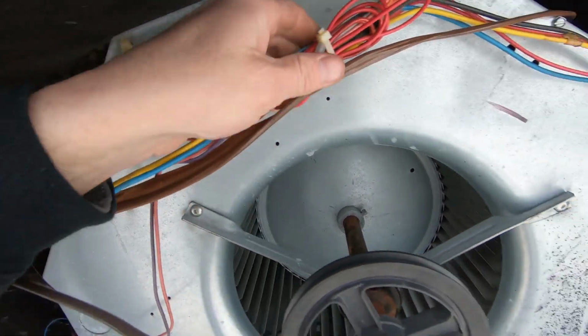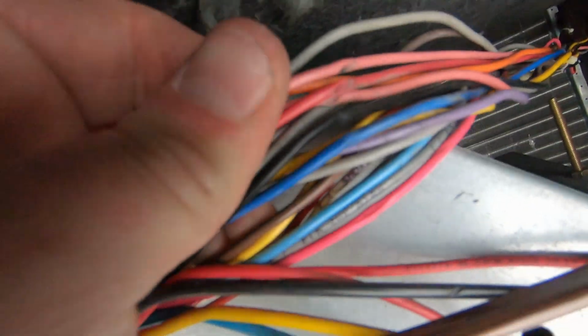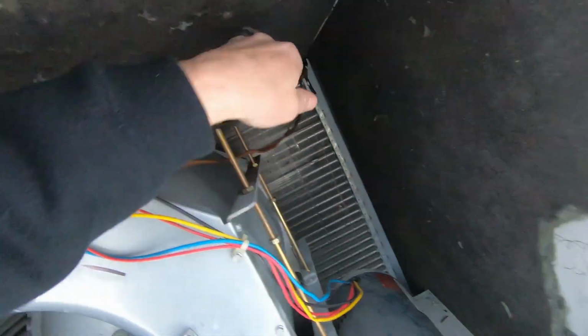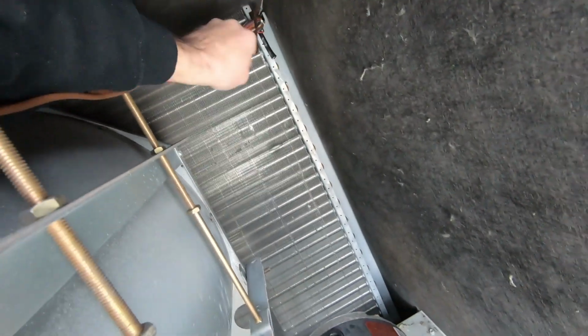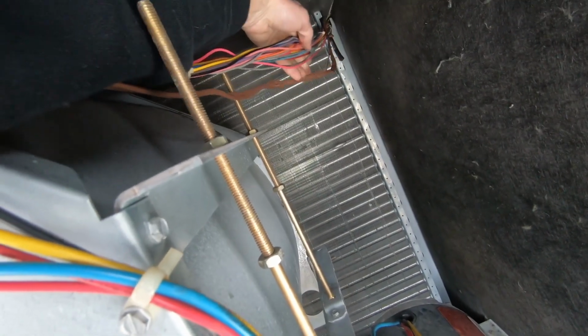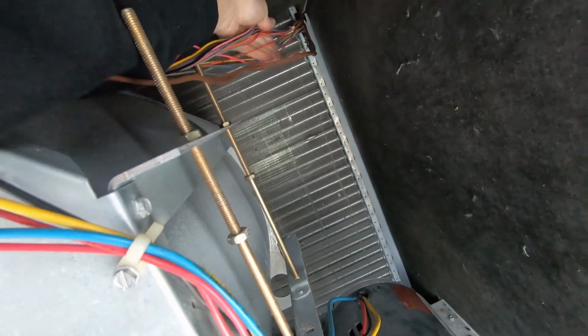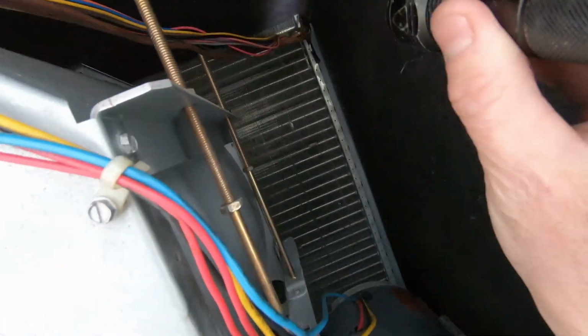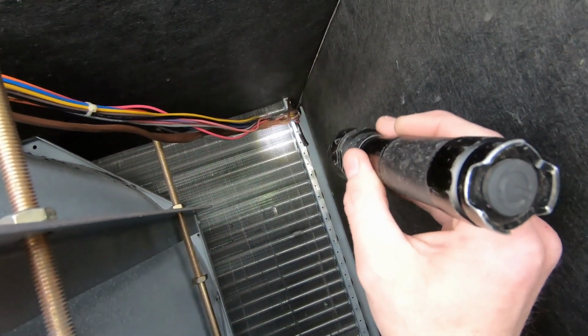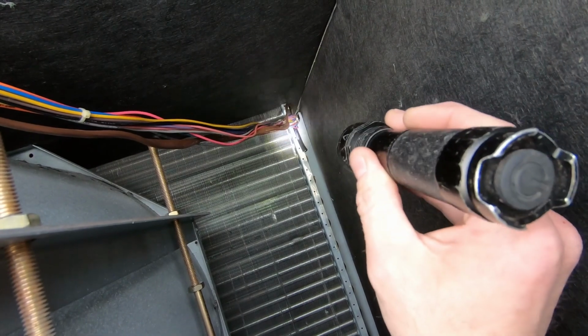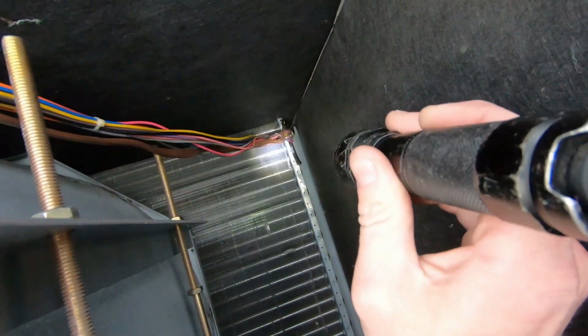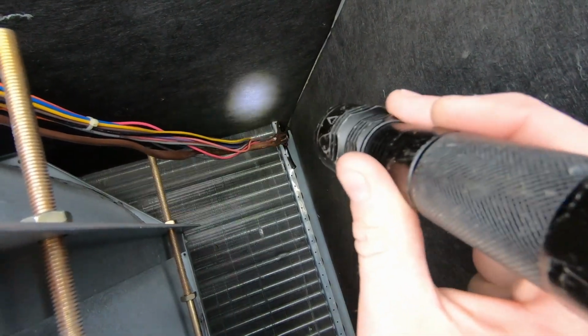It doesn't appear that they're melted so badly, but these ones clearly got hot because you can see the indentation of where they rounded this corner. I mean, this wire's melted, it's brittle. Brittle and melted. It's melted to the plastic. It's all melted together back here. Those wires, they're melted to that plastic safety cover that goes around. So before I fire anything up and apply any power, this thing needs a good thorough inspection of the wiring, period.